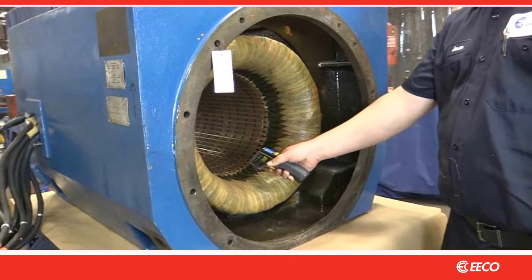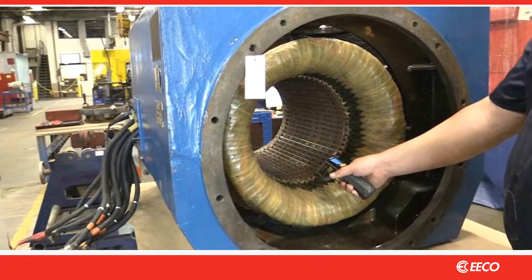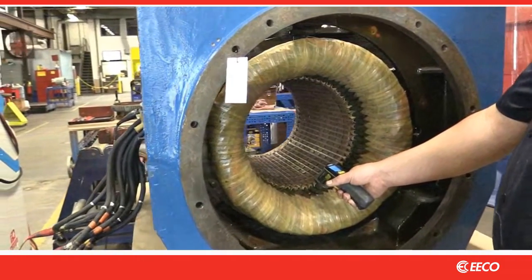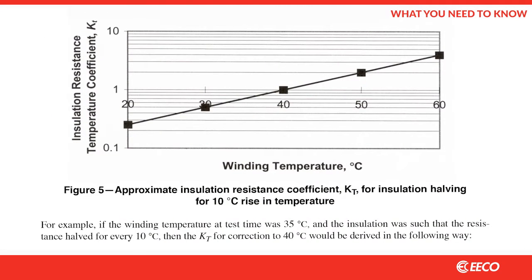Whether in the field or the repair shop, temperature must be considered when conducting an insulation resistance test. With every 10 degree centigrade change in temperature, insulation resistance changes by a factor of two. For example, the insulation resistance of a motor recorded at 30 degrees centigrade would read half that in megaohms at 40 degrees centigrade.